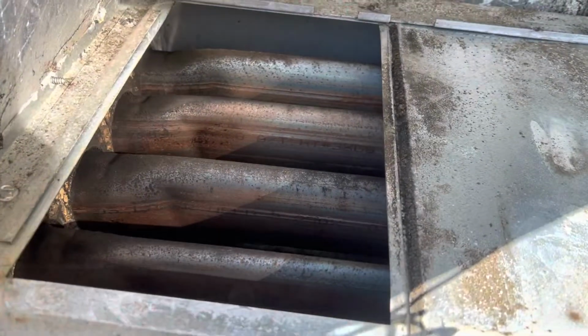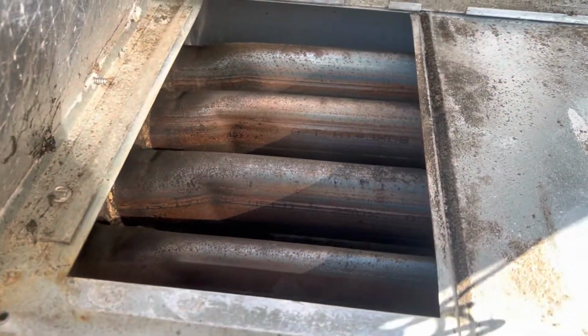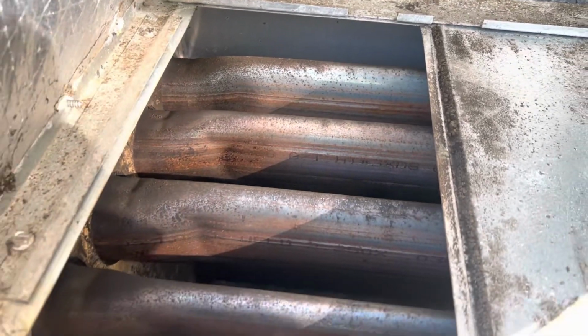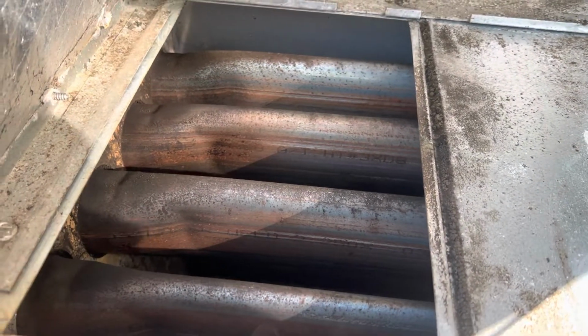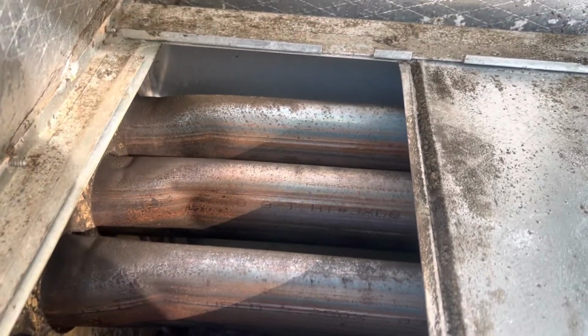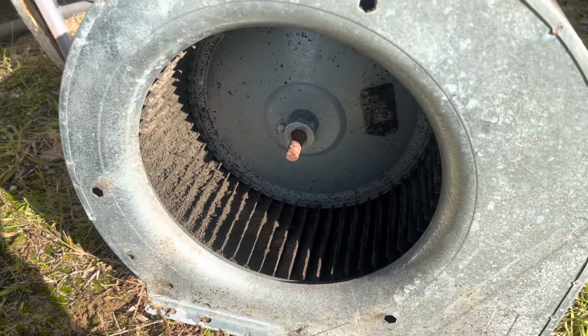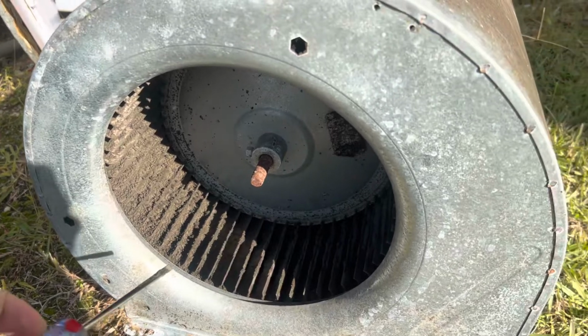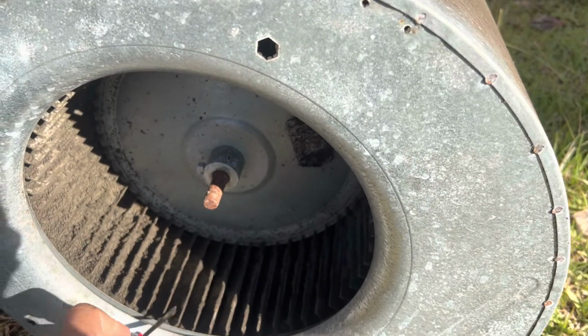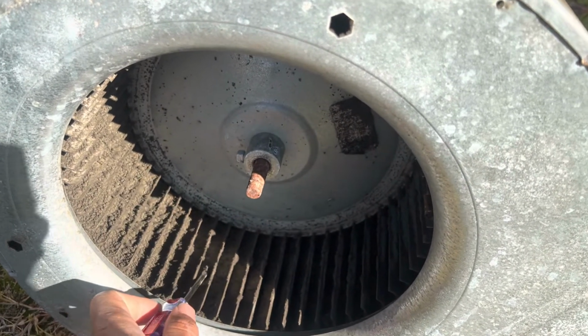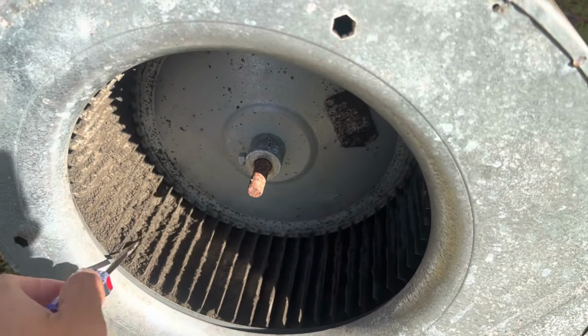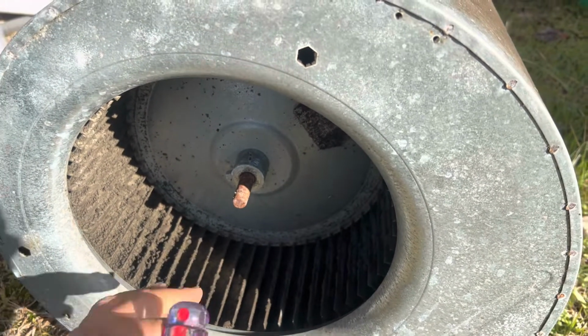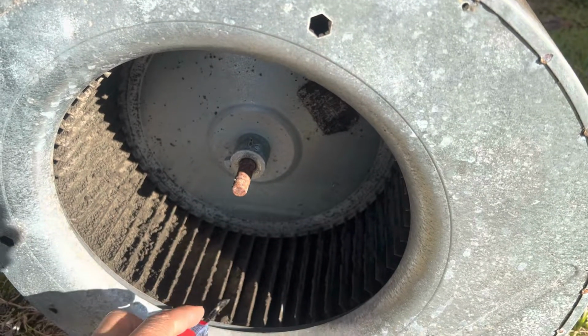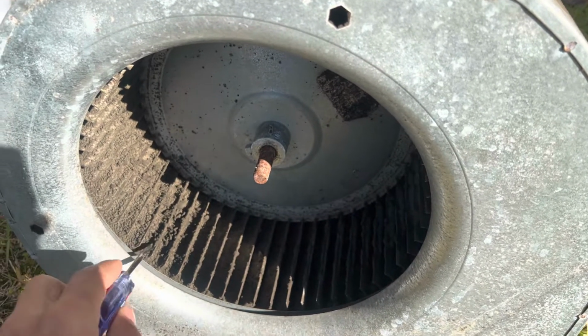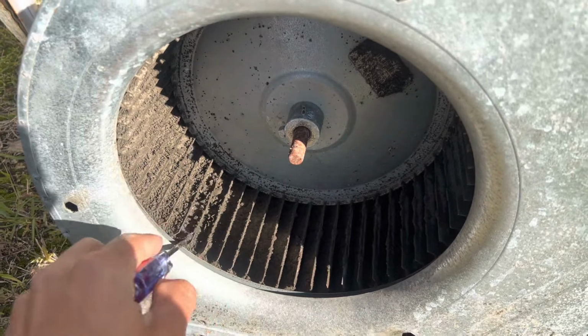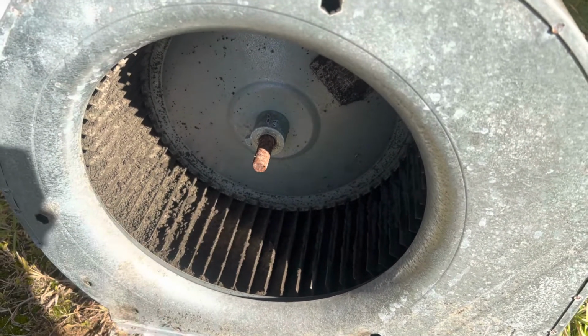Okay, there's the heat exchanger there. All right, so what we're gonna do is we're gonna check for any obvious cracks on there. Okay, so the heat exchanger looked good. Now, since we have the fan out, you see all that dirt in there. That causes a lot of drag, which will burn this motor out. Also, you don't get good airflow, so we're gonna wanna get all of that dirt off of that squirrel cage.